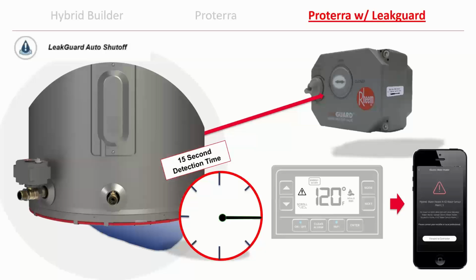The other thing is that shutoff valve is going to cycle itself. Once every few days, it's going to cycle on and off a few times, and it usually does it in the wee hours of the morning when nobody's using it. And what that's for is to keep that ball valve working, because if you're familiar with ball valves or any kind of valve really, after it's set in a water line for a prolonged period of time without being exercised, they're going to freeze up from calcium and lime buildup on them. This exercises it frequently so it keeps that valve good and working.